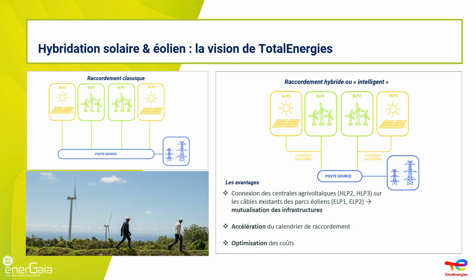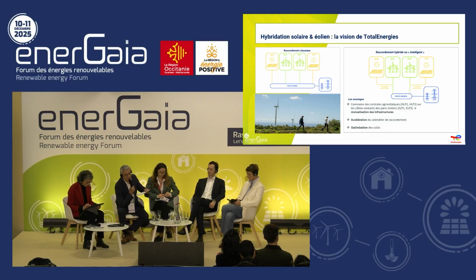If we go to the following slide, mostly it's the same principle we've just heard. We have a little bit of residual capacity in the cable. These are projects each taken separately with their own source substation, purchase contract, and obligation for separate connection. We have a wind farm of 11 megawatts and an evacuation capacity of 12 megawatts. There's 1 megawatt left, and we want to connect one of the two PV projects—the one that is 3.6 megawatts—to this residual 1 megawatt.